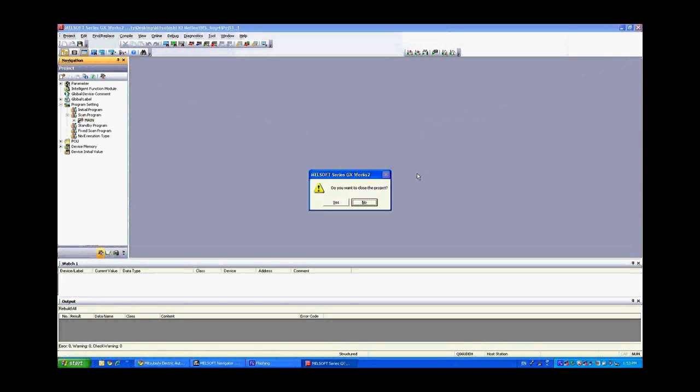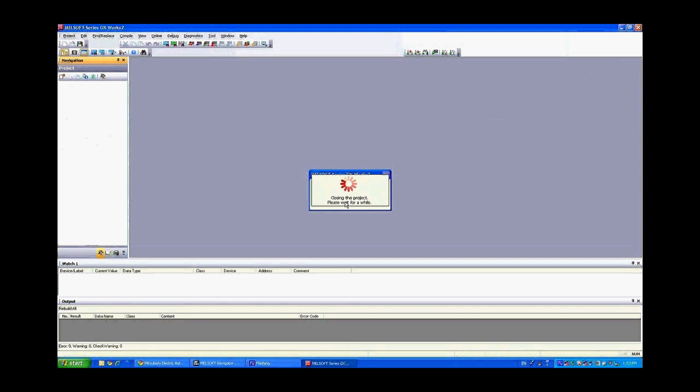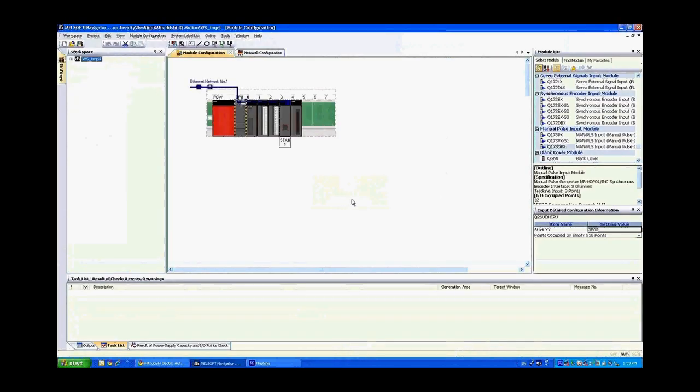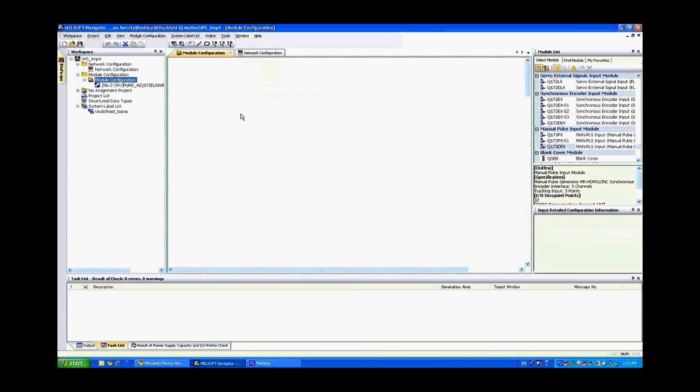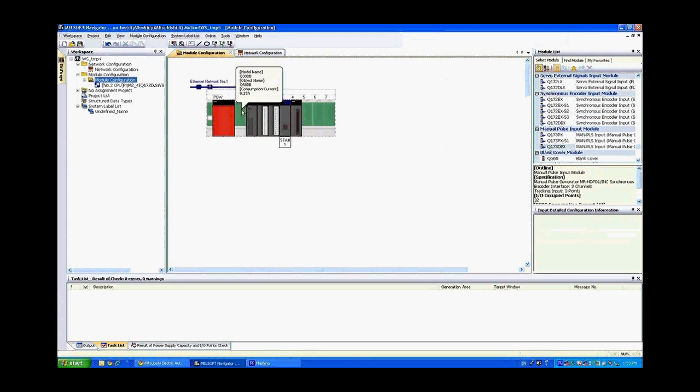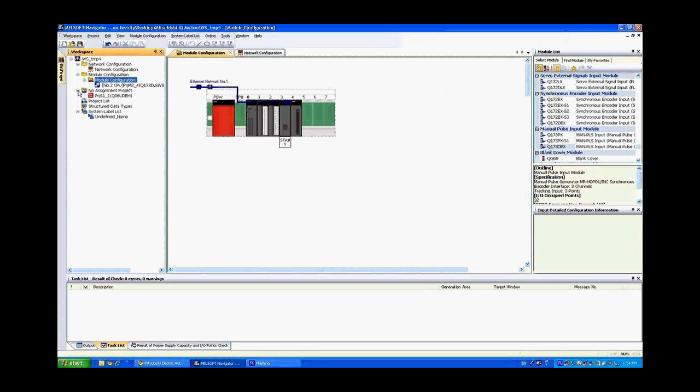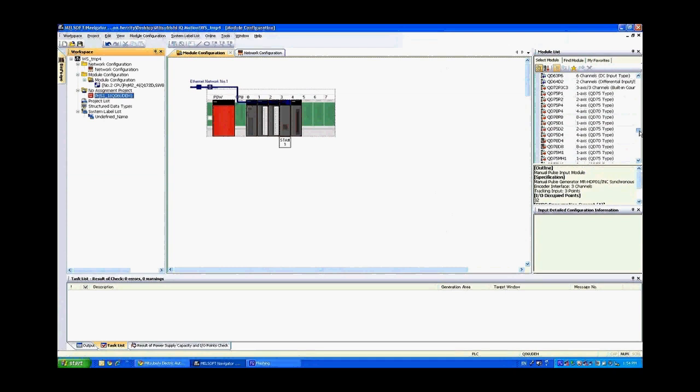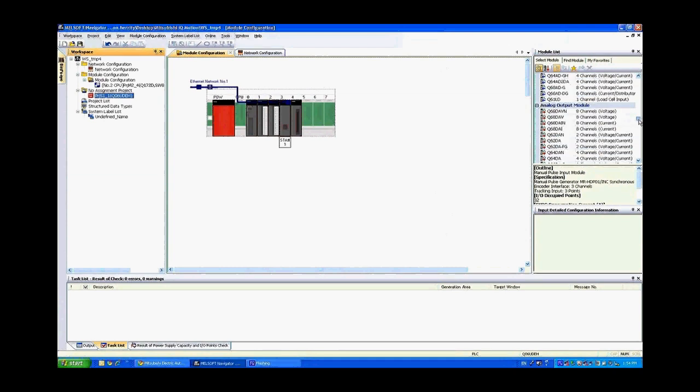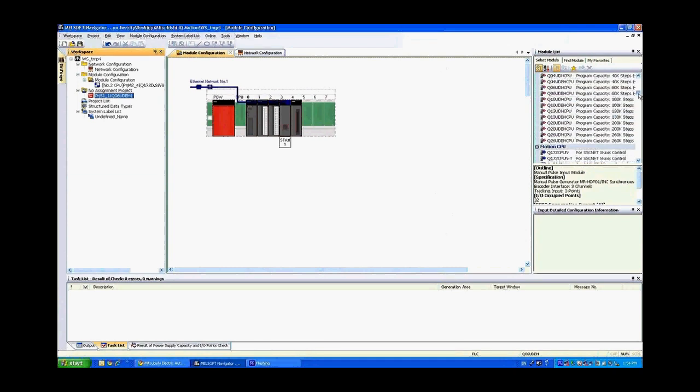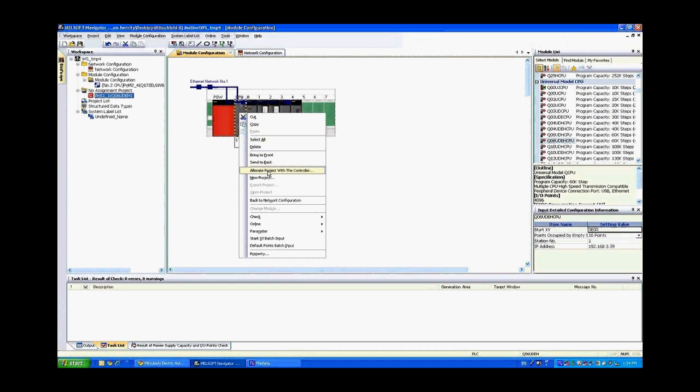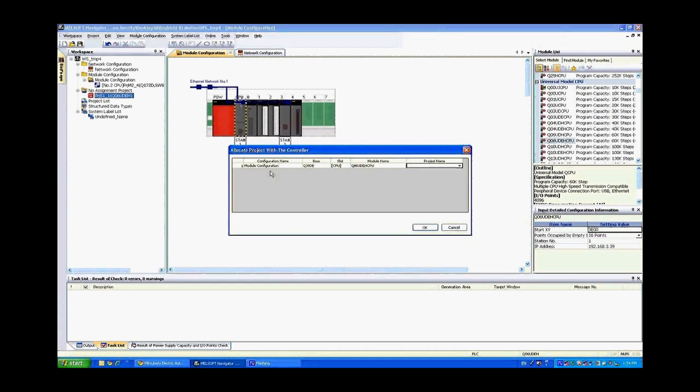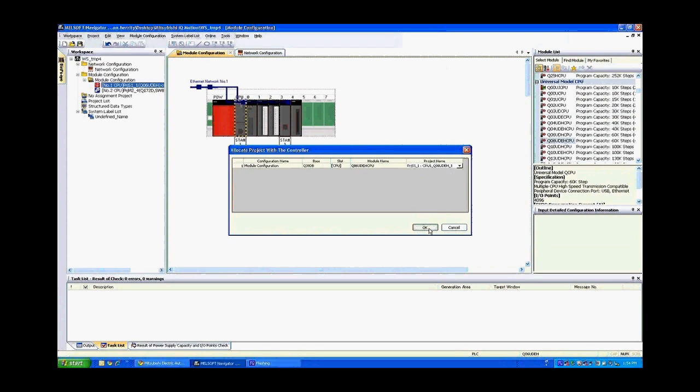Now that we're back in here we still have the Q26UDH CPU. We do not want that. So let's go ahead and delete that PLC now. You'll see that that project that we just changed hasn't been assigned. However it still maintains all the labels and all the settings that were originally configured with the motion template that we set up. So if I expand the no assignment project you'll see that this project is sitting here unassigned. So I'm going to grab a Q06UDH CPU, go all the way up to the top here, drag this over into the rack and if I right click on it I can allocate project with controller. Now here in my project name I select that unassigned project to this PLC and I click OK.